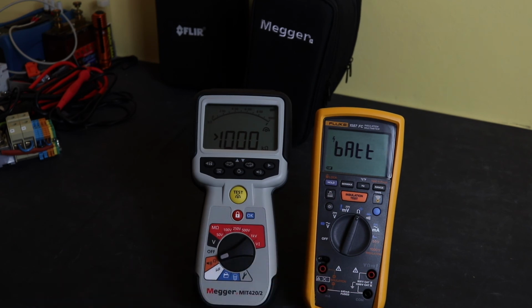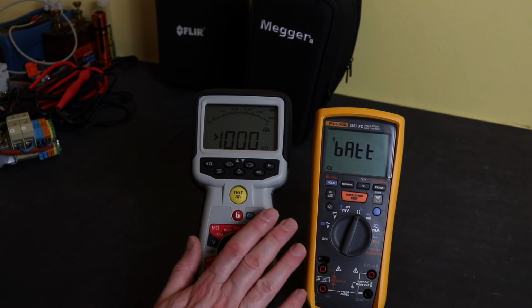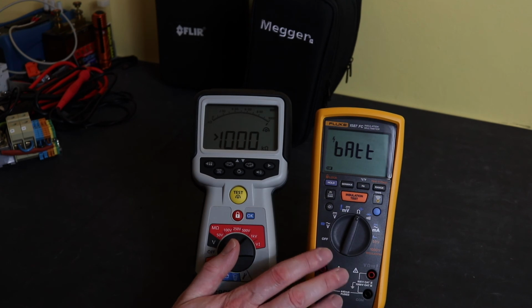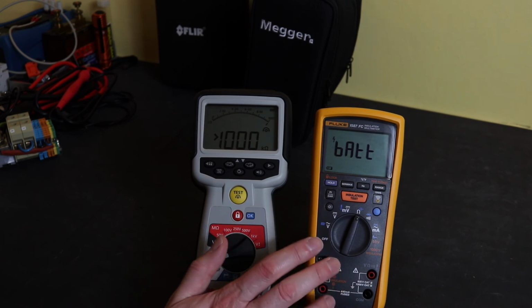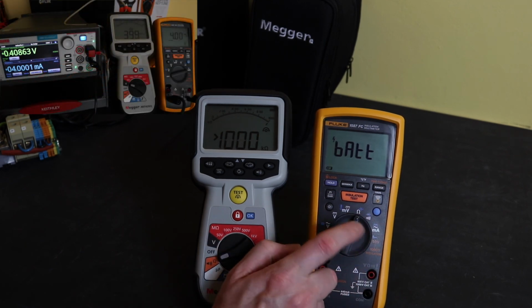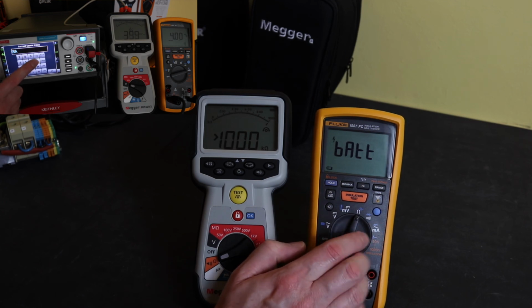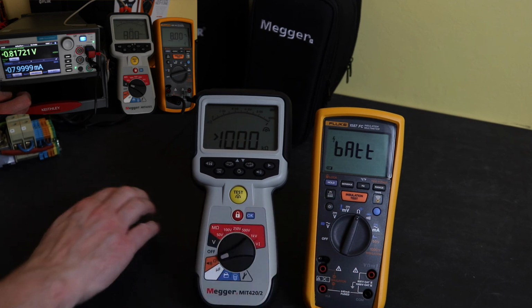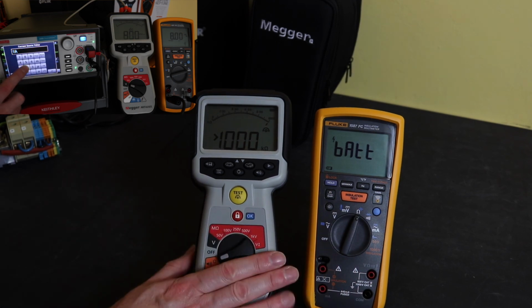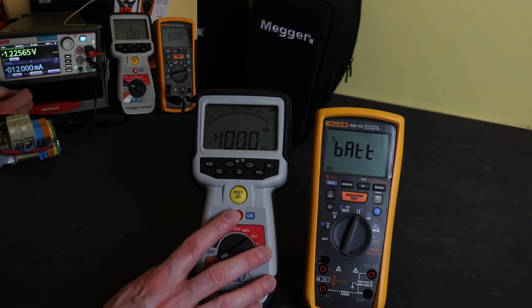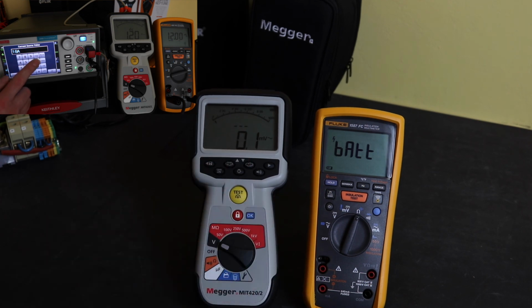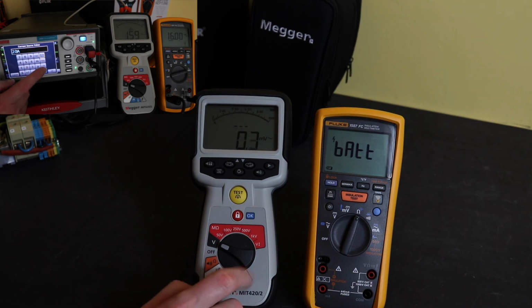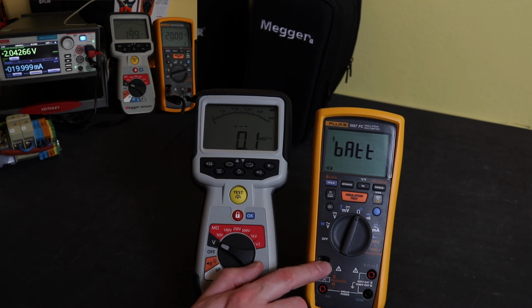The Fluke also suffers when you test the output stability of the insulation test function in comparison to the Megger. Where the Fluke does outperform the Megger is the general voltage readings and the resistance readings. They are more accurate, and also when you test a transducer, the milliamp function on this for transducer testing is excellent. It's on a par with specialist instruments that I use for testing transducer outputs, really. Very nice. The Megger here can do that using a load resistor and measuring the voltage. It's got a good millivolt function there. You can see it can measure down to 0.1 millivolts, so with the 100 ohm load resistor you can get a reasonable test of the transducer output, but in comparison you choose the Fluke for measuring transducer outputs every single time.